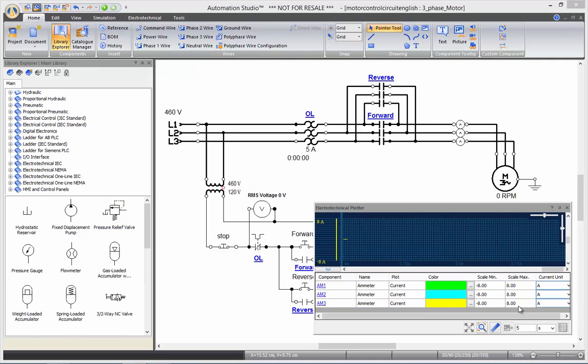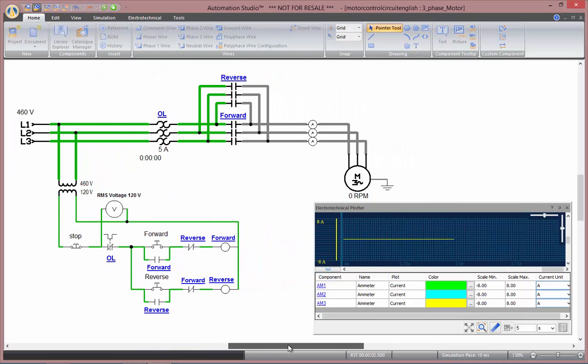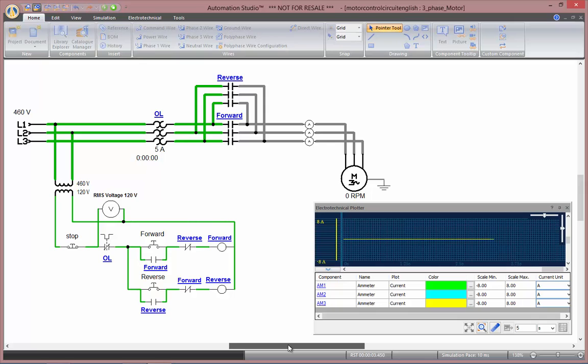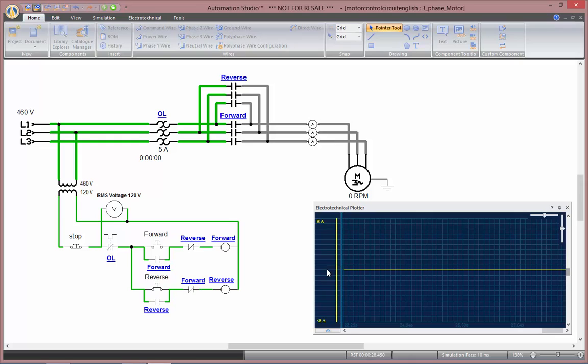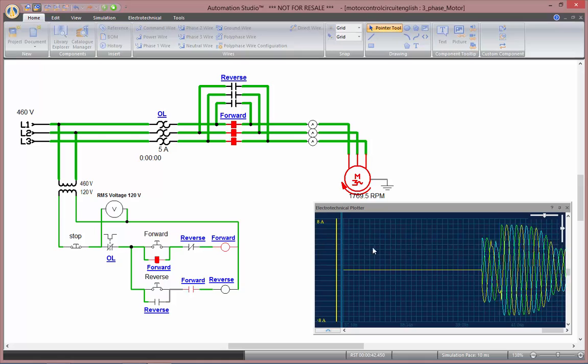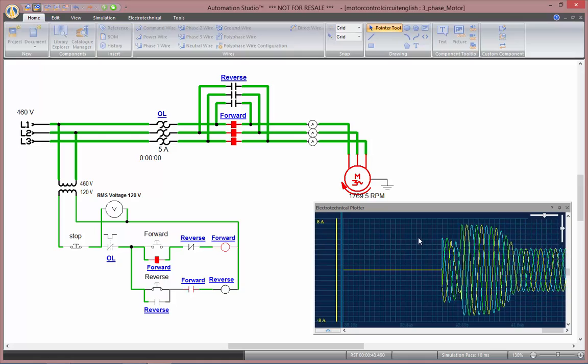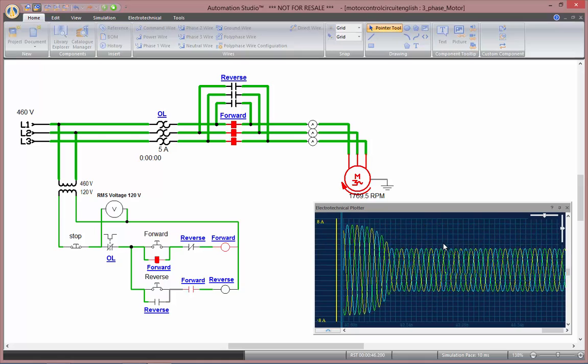Now that we've finished configuring our plotter and scale the different ammeters, we can go to simulation. You can minimize the details of the electrotechnical plotter so you can see the graph bigger. Now, as I press forward, you'll see the motor starting to turn and the current consumption start high and then reduce as the nominal speed is reached. And you see high current consumption that fades down to nominal speed.